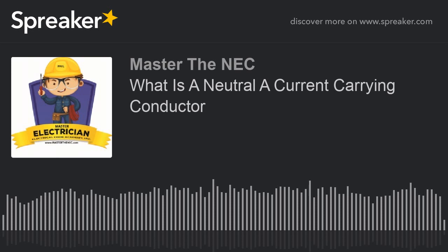All right. So at the end of the day, if you have a single phase 3-wire circuit, as we talked about earlier, just a single phase, in that scenario we've got 10 amps on the black. We have 15 amps on the red. Then the unbalanced current is going to be 5 amps on the neutral. And obviously that neutral is going to carry quite a bit less, and it's not going to provide an overheating process. It's going to contribute some heat, but not enough that has to be worried about as far as the code's concerned. So you don't have to count that neutral as a current carrying conductor.